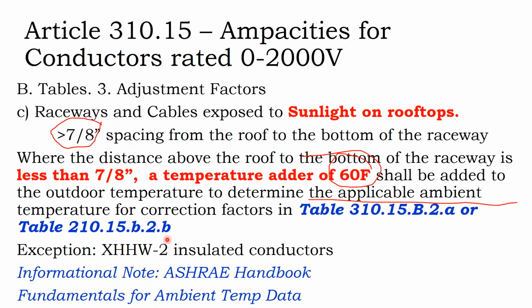And so those are the gems on why it's worth going through the electric code, particularly if you're brand new to any kind of electrical work. It's a lot to learn. When you have more than 3 conductors in a conduit, you discount 20% for 4 to 6, then 50% for 10 to 20, and then by a lot, 65%, for more than 41.